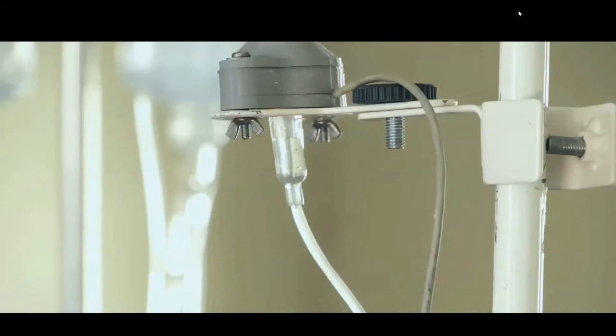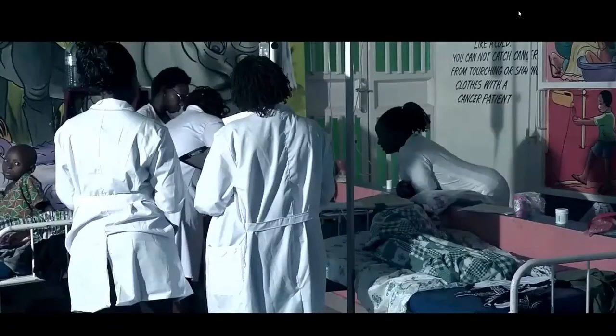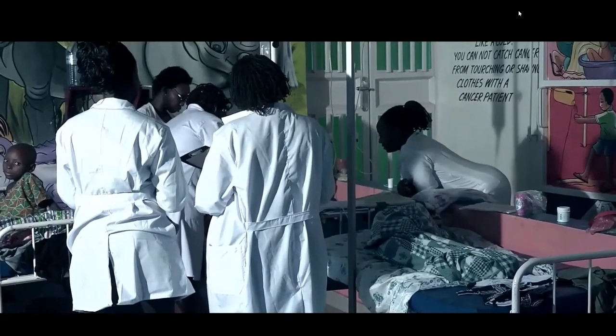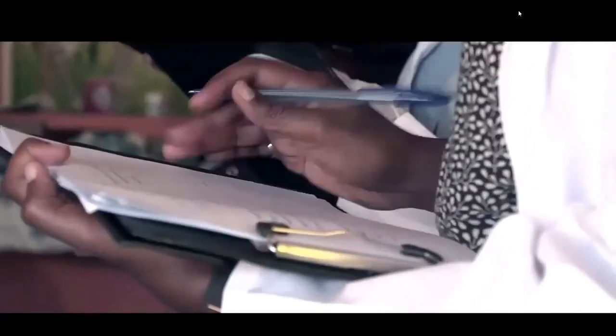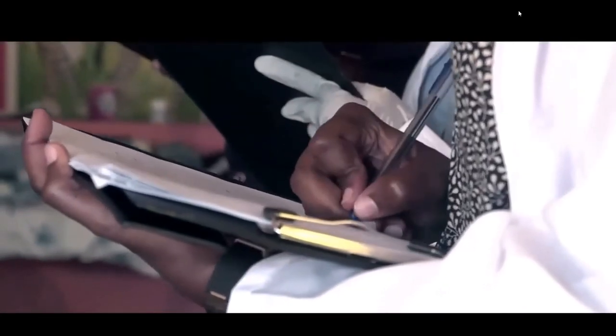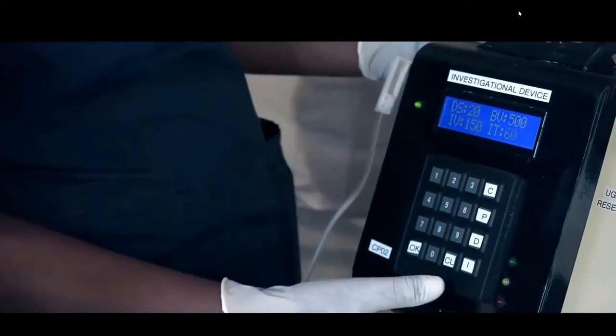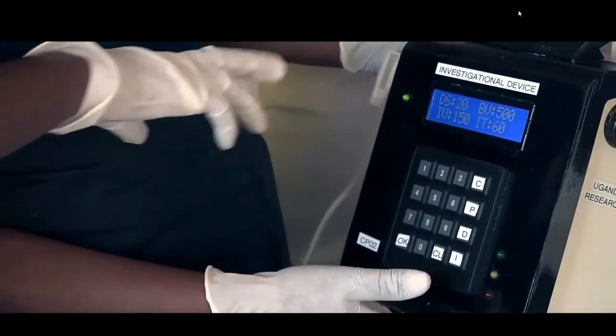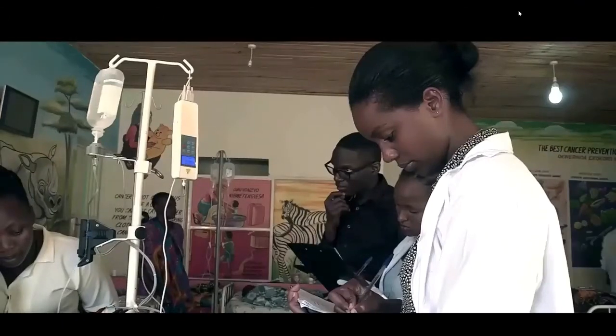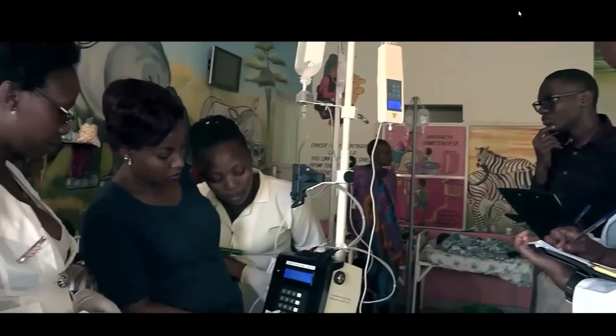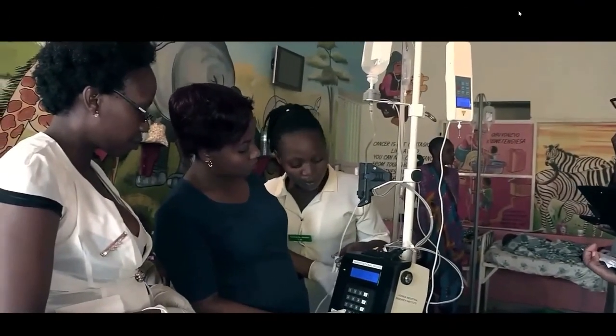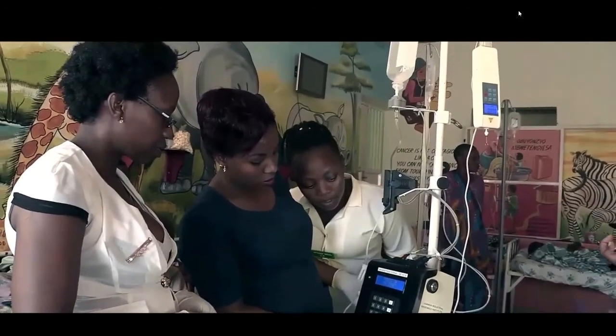We've been able to pre-clinically test the device against medical device standards, and it performed at plus or minus 1% as its error margin or accuracy, which is the deviation between the actual and the prescribed flow rate. In addition to that, we were also able to carry out our first clinical pilot in adults with infectious diseases, which was conducted at Mulago Hospital at Chirudu, and we were able to attain an error margin of plus or minus 7%.